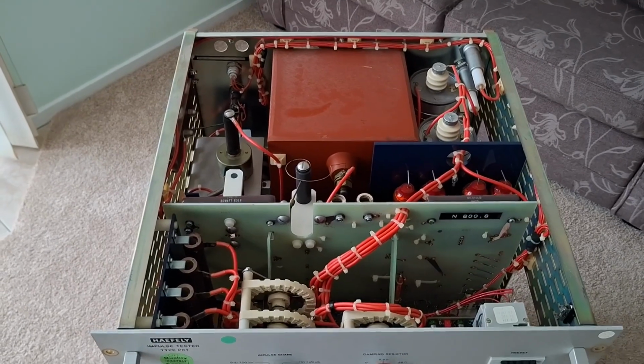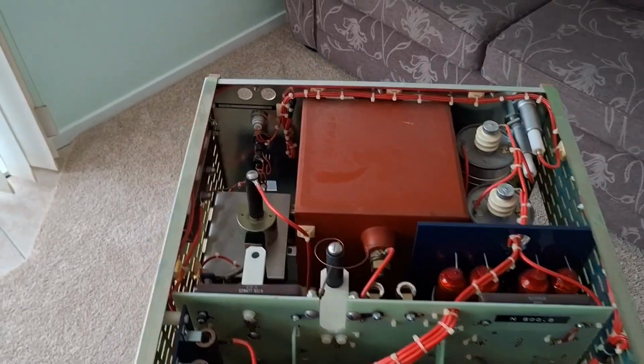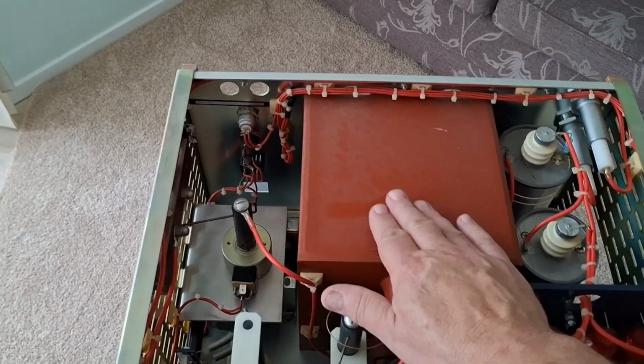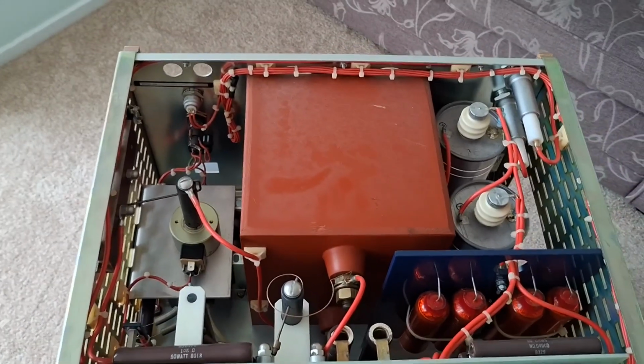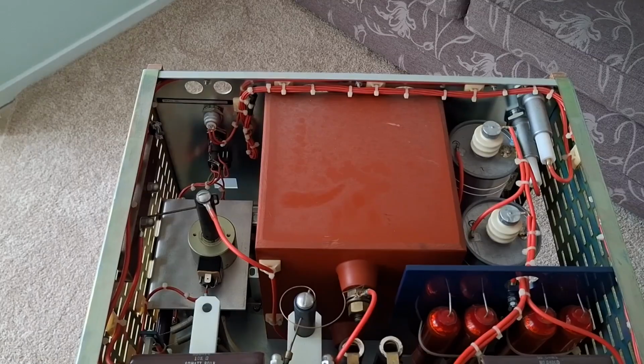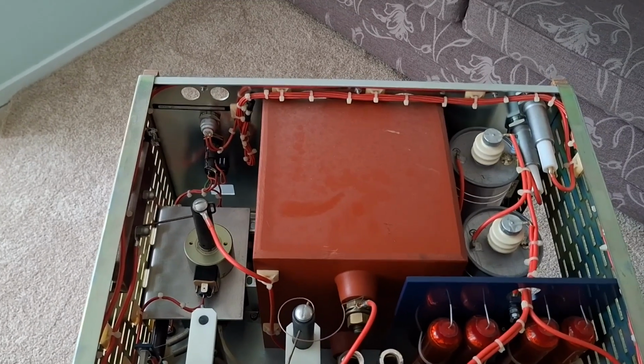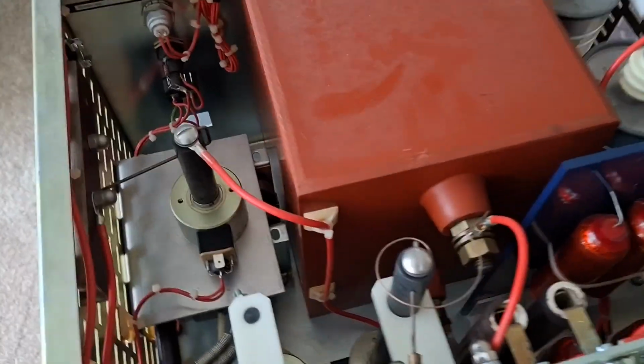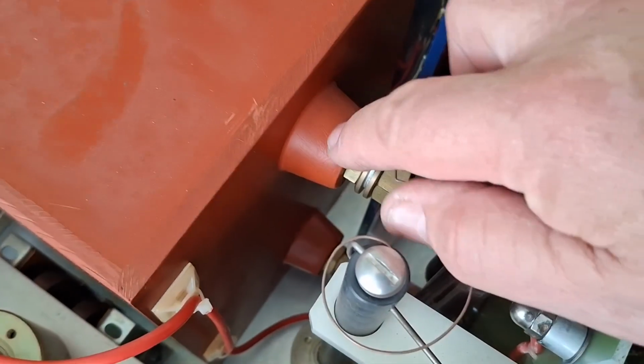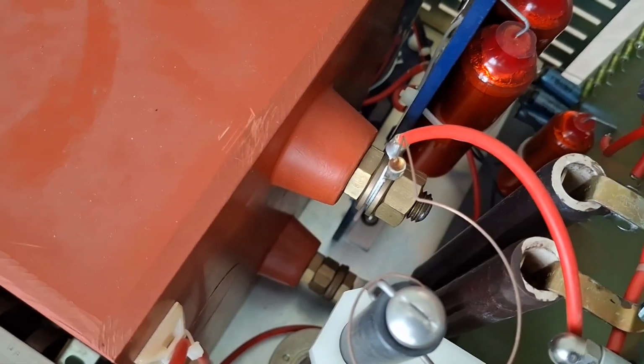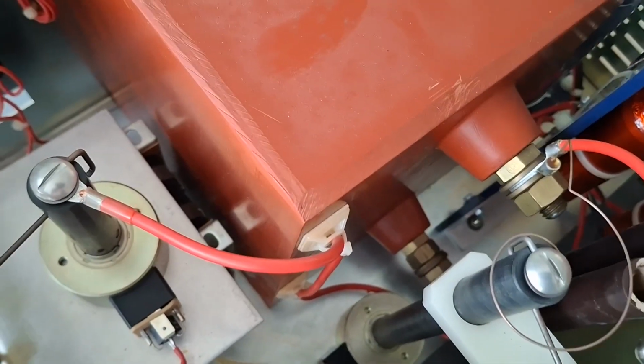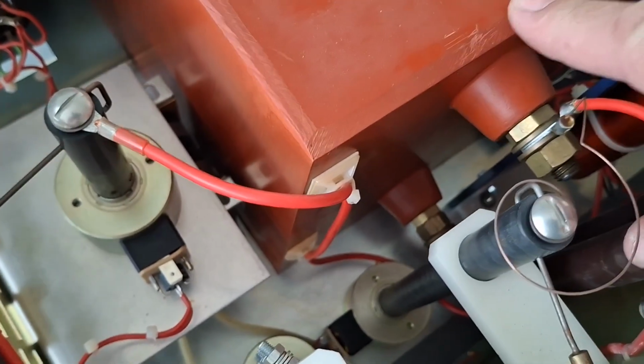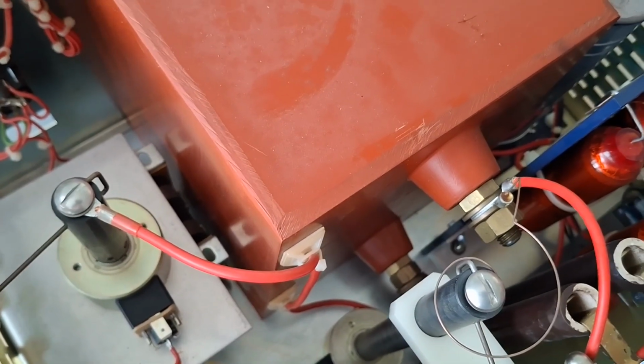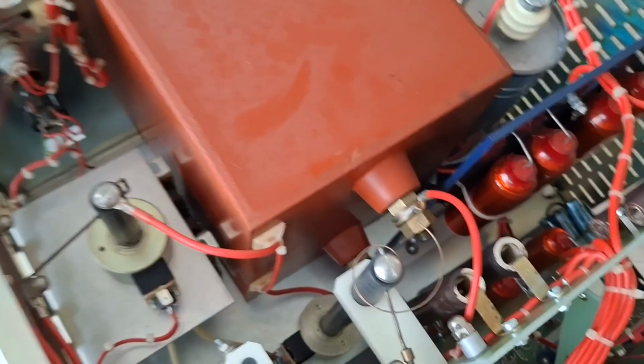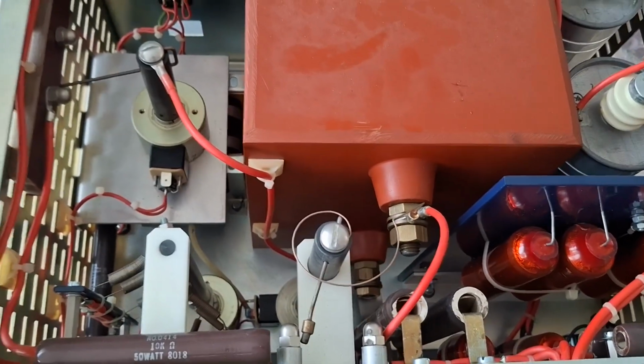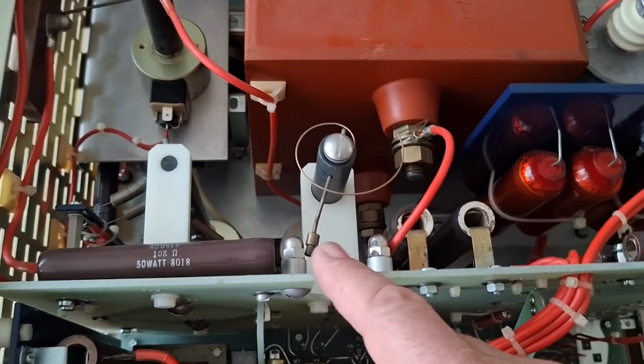Well, if we take a look at what's inside, what's under the covers, the thing that dominates the whole of the enclosure is this device here, and this is a 20 microfarad 6 kilovolt capacitor. I know from previous experience this is oil filled, so what I'm looking for here is if there are any leaks around the glands, and I can't see any, which is a really good sign. The enclosure is fully welded along all the seams, so unless there's a flaw in the weld, there shouldn't be any oil leakage anywhere. So that's checked out. That connects into a high voltage switch, which is this device here.